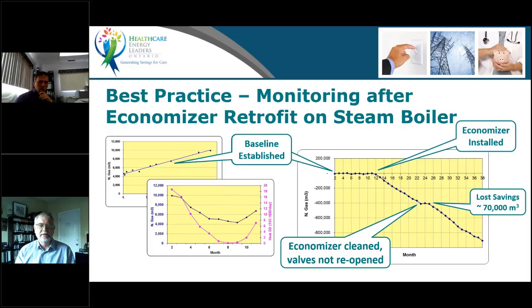What happened was that the economizer needed to be serviced one year in. So they shut down the boiler, valved it out, took the economizer out, cleaned it, and put it back in. Then they restarted the boiler and didn't open the water valves to the economizer. So there was significant lost savings. But had you been monitoring that, even on a weekly basis, you would have caught it. That's 70,000 cubic meters of lost savings. So monitor, even after you've got this technology, good monitoring really pays. Back to you, Michelle. Yep.